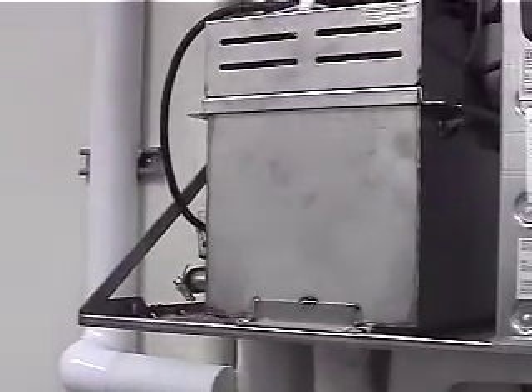Typically the biggest problem we have is people don't clean these tanks enough. They build up with some scale. You guys call me, some humidifier doesn't work. I come out, open it up, yep, but it doesn't. And I can't answer how often these need to be cleaned because it's all dependent upon your water quality here. I don't know if we're running softened water to them, do you guys know? Or if it's regular water, depending on how much it is used is going to depend on how often it needs to be cleaned.